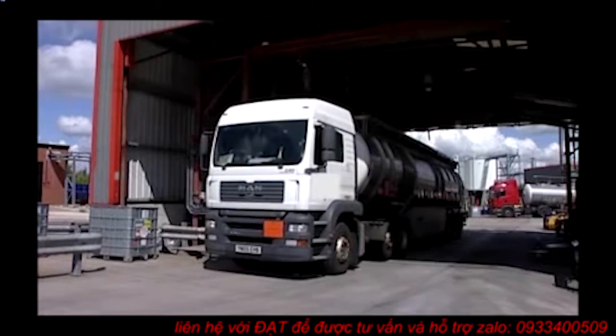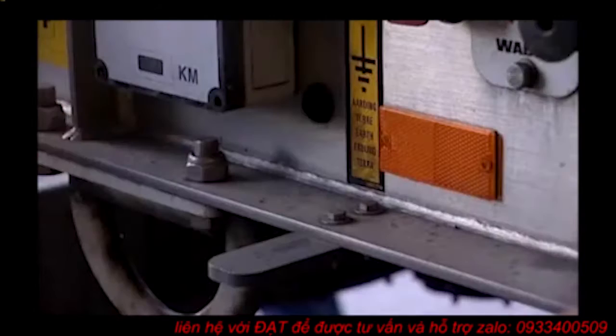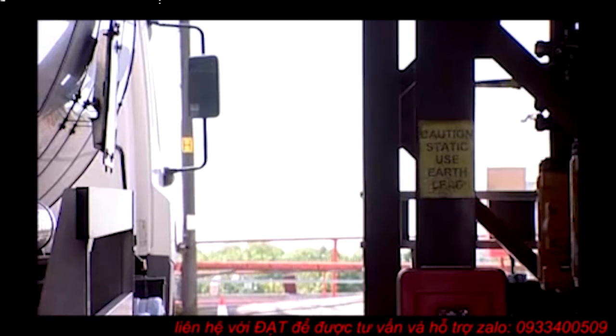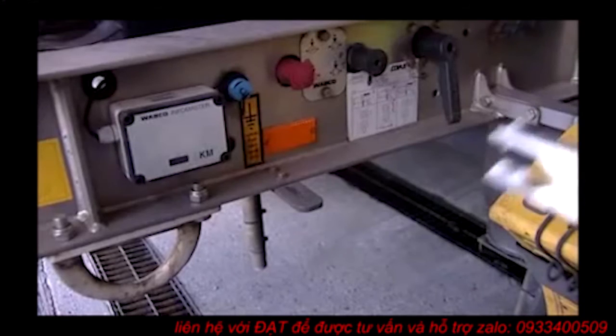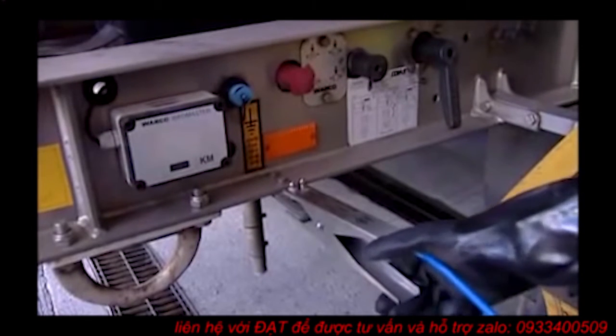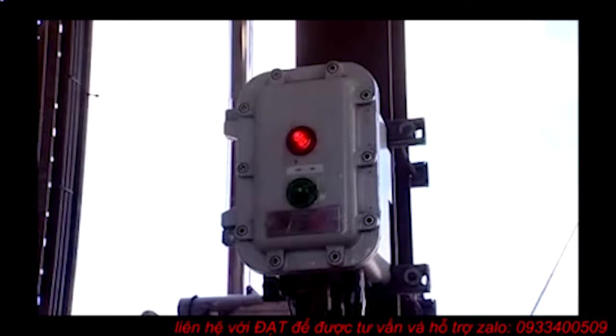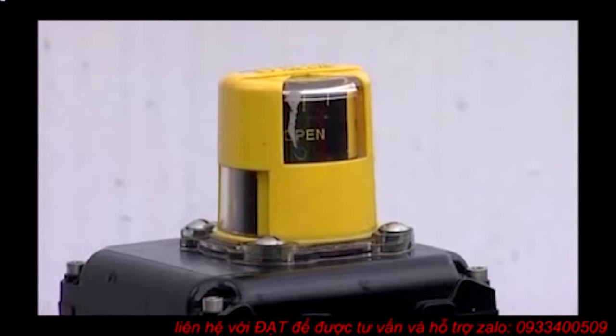When filling road tankers, special earthing conditions must be made, as the resistance to earth of a vehicle can exceed the recommended maximum resistance. In all instances, the earthing clamp should be attached to the vehicle before any other operation, and should not be removed until all operations are complete and there is no presence of vapor.